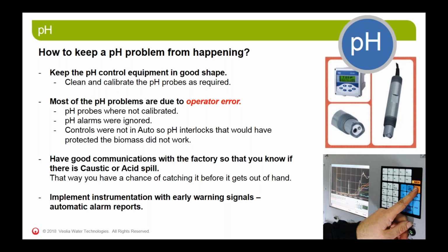Also, operator error can be a problem. If you're not calibrating the probes like you should, that's an operator problem. Also, I can't tell you how many times I've heard about customers having a pH problem, and my first question is, did the alarm go off? Because 99.99% of our plants now have control packages where alarms are set, and the operator has the ability to change the alarm set points. And there should always be a high alarm and a low alarm that somebody should see and acknowledge, and should be able to then take action before you get to a high or a low alarm.